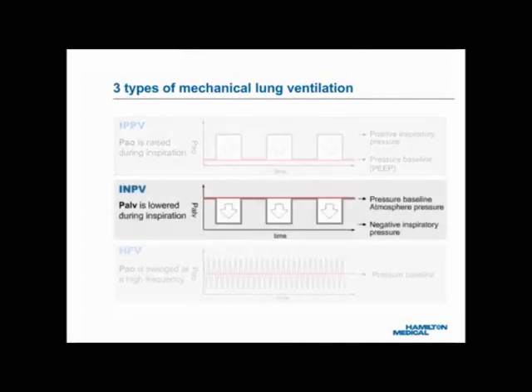Two: the center graph shows the pressure waveform for INPV, or Intermittent Negative Pressure Ventilation. Using this principle, a negative alveolar pressure, or PALV, is applied below the pressure baseline. The negative PALV sucks air into the lungs. The baseline is usually local atmospheric pressure.